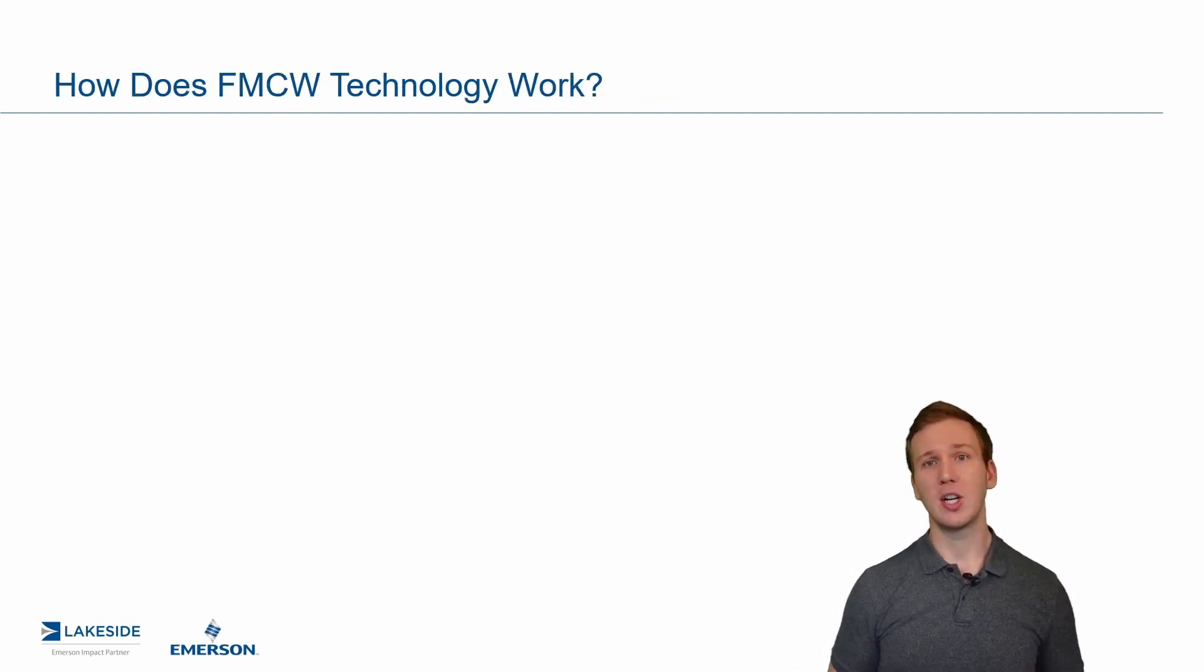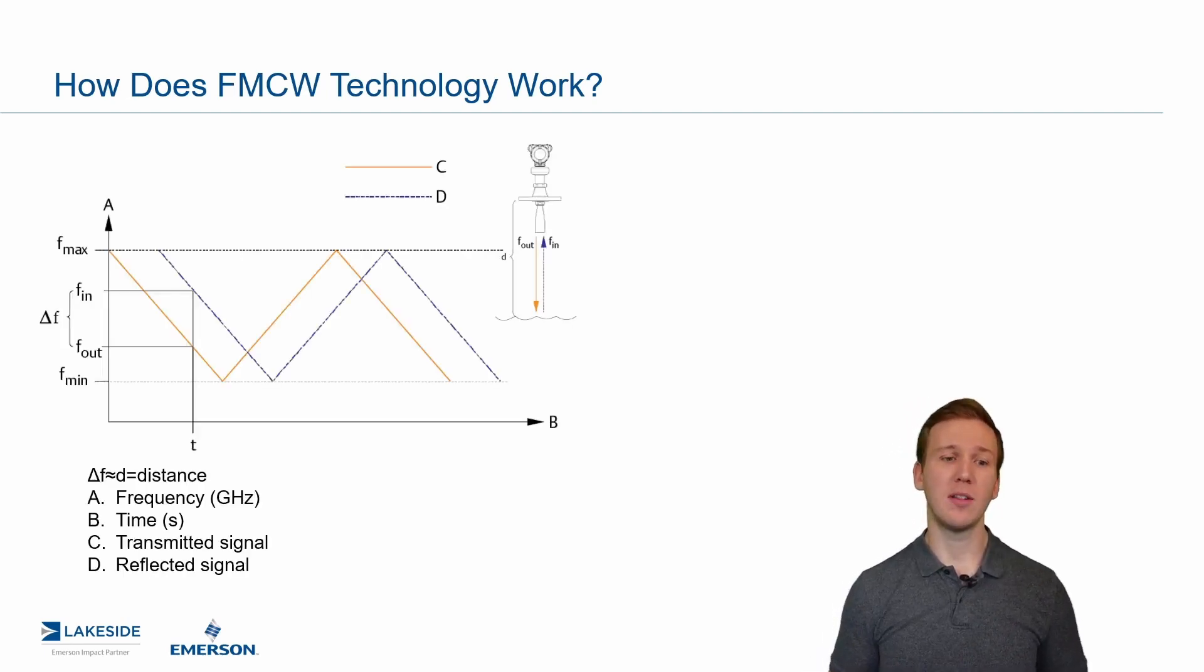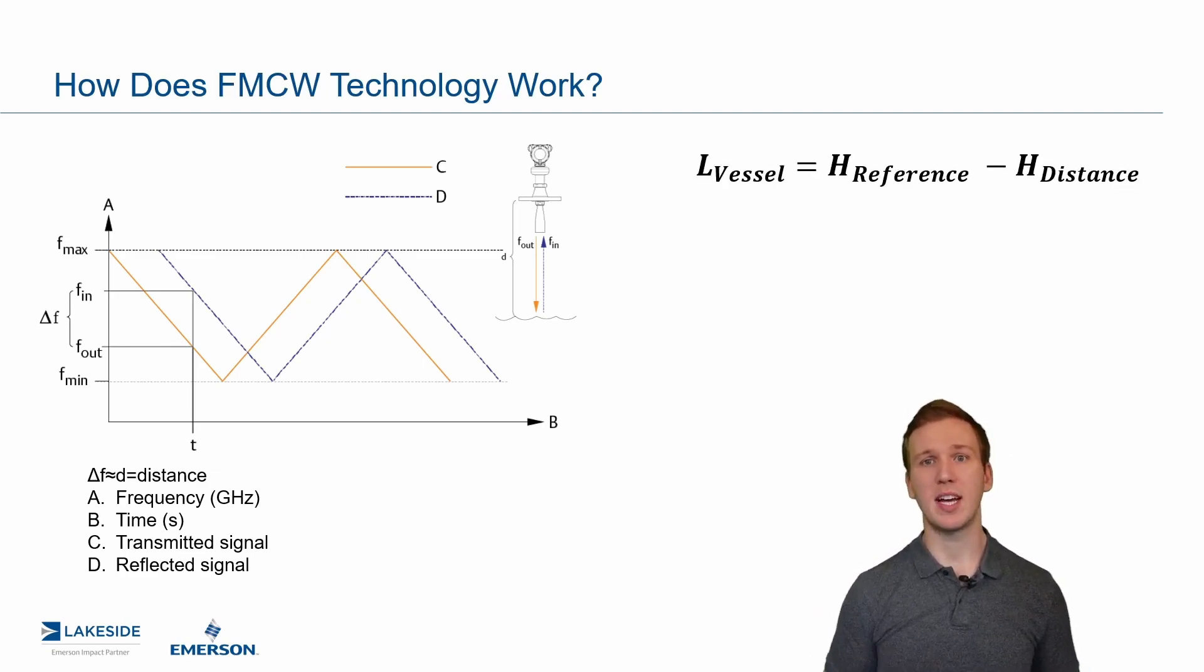Now, we actually look at something slightly different. Instead of measuring how long it takes, we look at something called the phase shift difference. We look at the frequency as it's emitted versus when it's received. We look at the distance between these two wavelengths. This phase shift is directly proportional to how far the product is away. We still have to now reference that same reference height in the vessel and subtract that away, but now it's not based off of a time-of-flight measurement.